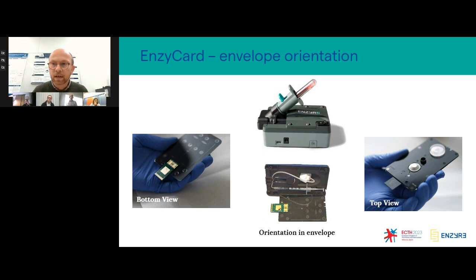As a second step, the blister is pinched and activated, and buffer is released inside the microfluidic cartridge as well. And by capillary force, the buffer and the blood plasma mix and transfer through the cartridge and absorb spotted reagents like proteins and phospholipids that are deposited in the cartridge as well. And ultimately, the mixture ends up in 16 detection chambers with a volume of about 100 nanoliter.